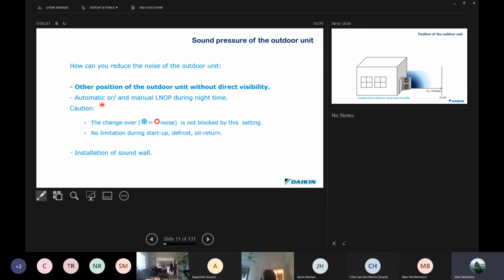Okay, Daikin also comes with our units an automatic or manual low noise during nighttime operation. So it's called low noise operation. This can be set up automatically through the condenser, which will look at the warmest part of the day, which is generally around 2 o'clock. It will add on a time period to that, and then you can set up starting times, say like 8 or 10 o'clock at night, and then it will switch off at a prescribed time the next morning, also done by adding on time. So it's not as precise as a real-time clock, but it's done by adding on hours according to that.